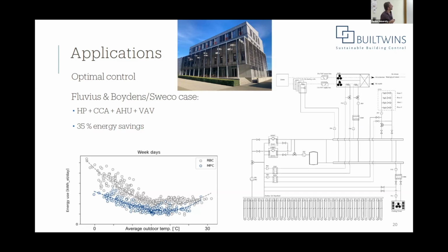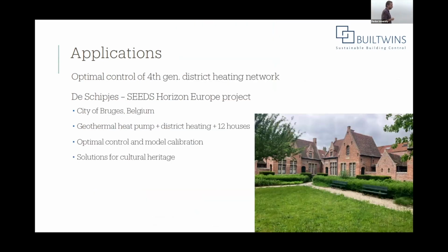I can't go into the details now, but there are VAV dampers for which we control the flow rate. We control the heating coil to heat one specific zone a lot, due to which the air handling unit can have a much lower supply air temperature. We need to use the concrete core activation more to have enough heat in total for that one specific zone that's too cold, and then the temperature of the heat pump is adjusted to get that peak power. So actually we're using relatively high temperatures, but the fact that we're not heating the whole building, just one specific zone, at the end of the day saves us a lot of energy.